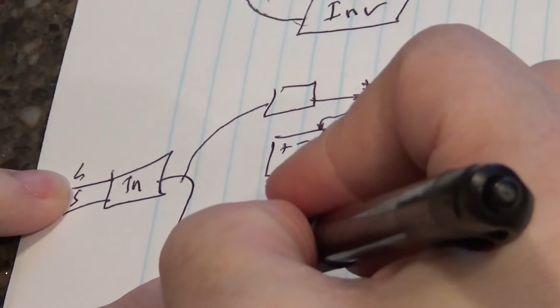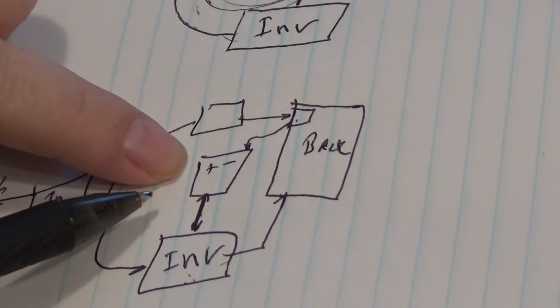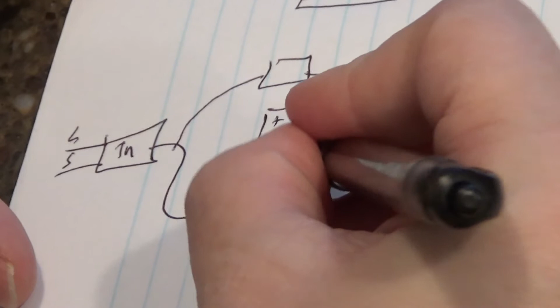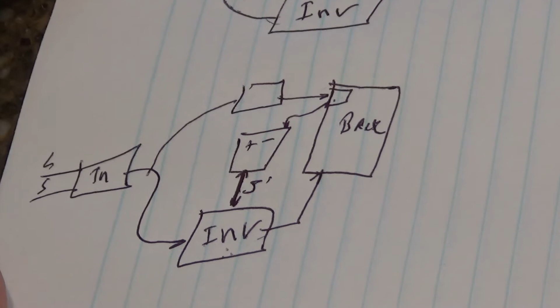Otherwise, it's off. This transfer switch, this inverter only sends AC to the breaker box. It only pulls from the battery when it senses there's no actual AC. So that's what we did. We moved the battery, instead of 25 feet, we moved it about 5 feet, maybe even less, with very big cables. That's what we did.